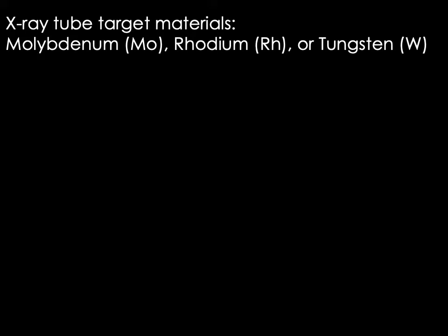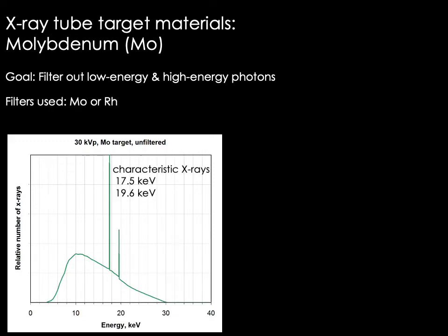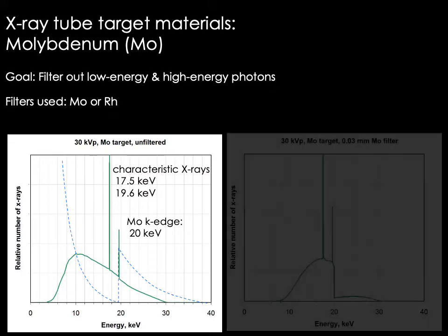The target or anode materials used in mammography are molybdenum, rhodium, and tungsten. For an unfiltered 30 kVp x-ray beam produced using a molybdenum target, characteristic x-rays are produced at 17.5 and 19.6 keV. As with other x-ray spectra, we want to filter out photons at the low and high ends of the spectrum. Molybdenum has a k edge of 20 keV, so a molybdenum filter absorbs many low-energy photons with decreasing absorption up to 20 keV, yielding a well-filtered x-ray beam.